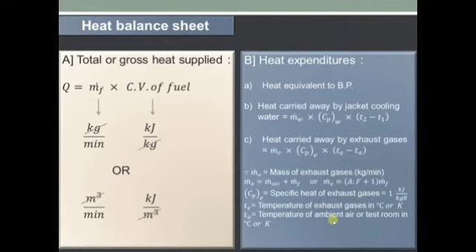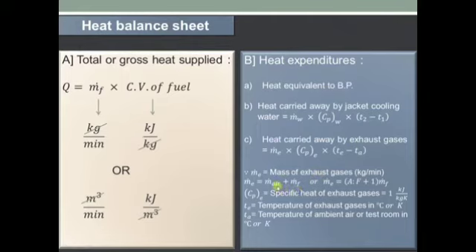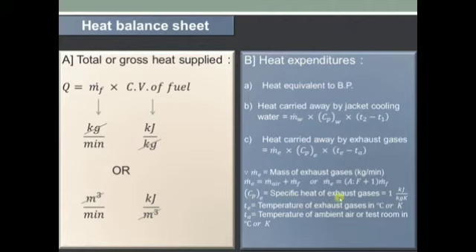Delta T is the difference in temperature, or the rise in temperature of the cooling water. Next is heat carried away by exhaust gases, that is Me multiplied by CpE multiplied by delta T. Me is the mass of exhaust gases in kg per minute. Me can be calculated in two forms: if mass of air is given, it is mass of air plus mass flow rate of fuel; and if air-fuel ratio is given, it is (air-fuel ratio plus 1) multiplied by mass flow rate of fuel. CpE is the specific heat of exhaust gases, equal to 1 kJ per kg Kelvin. T is the temperature of exhaust gases and TA is the temperature of ambient air or test room, both in degree Celsius or Kelvin.